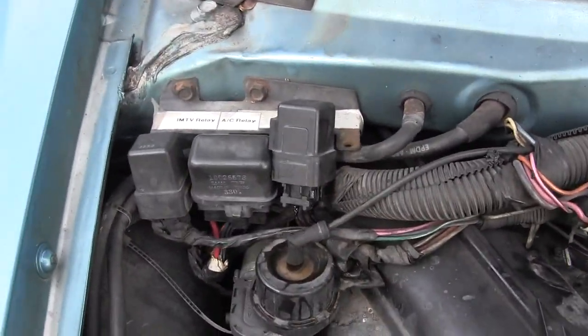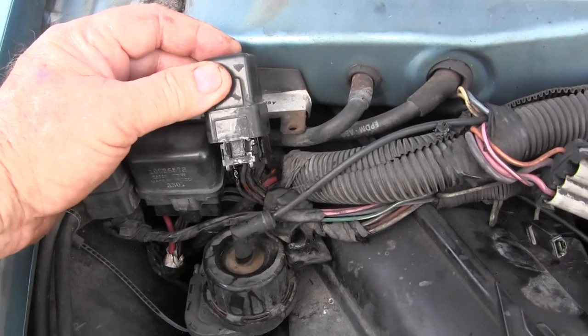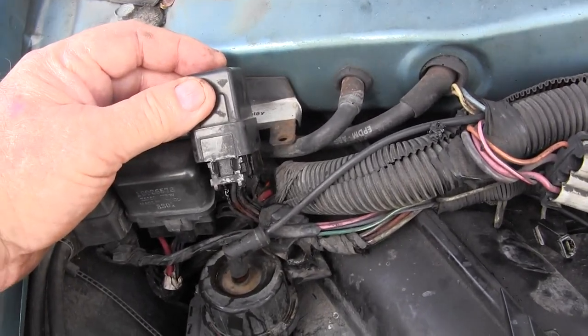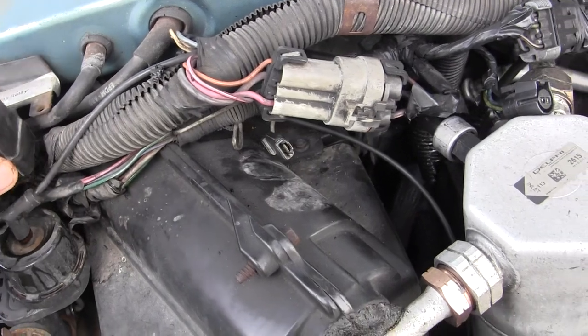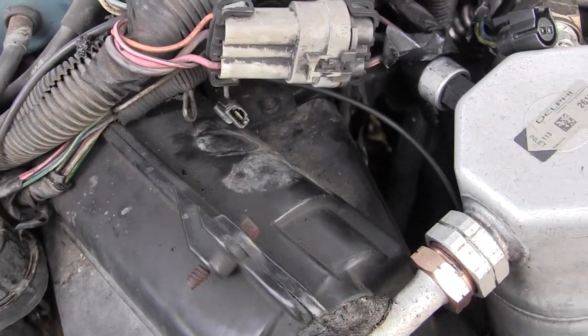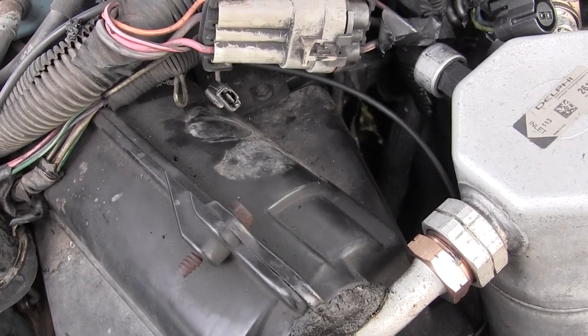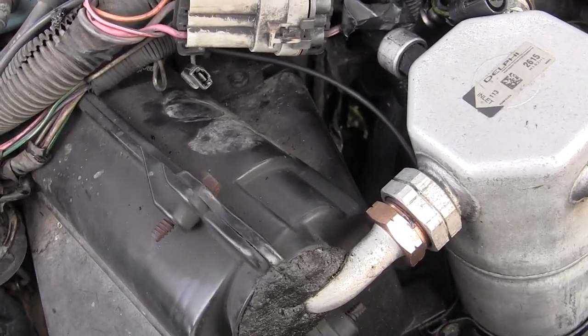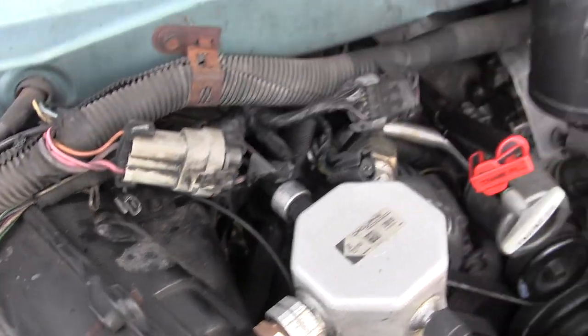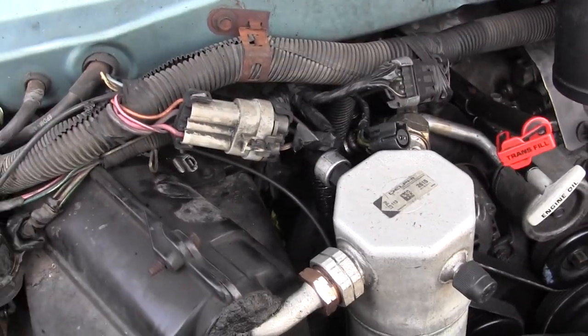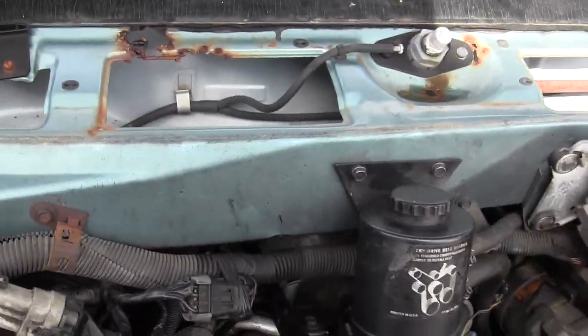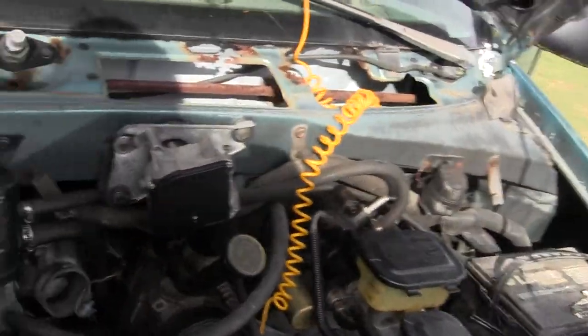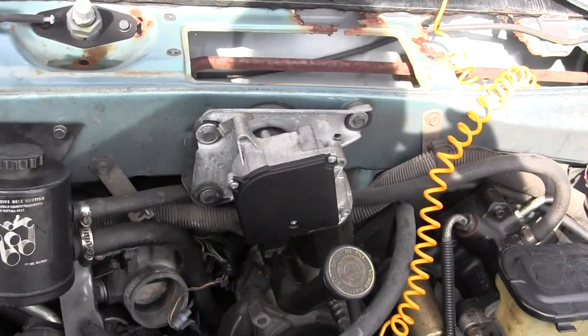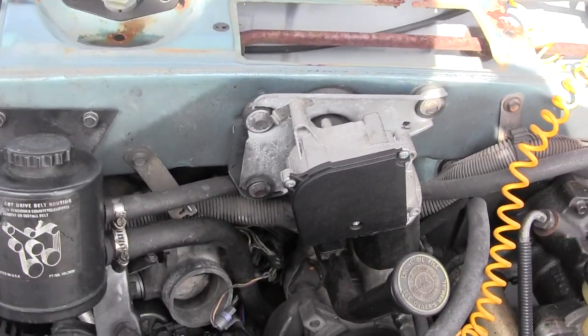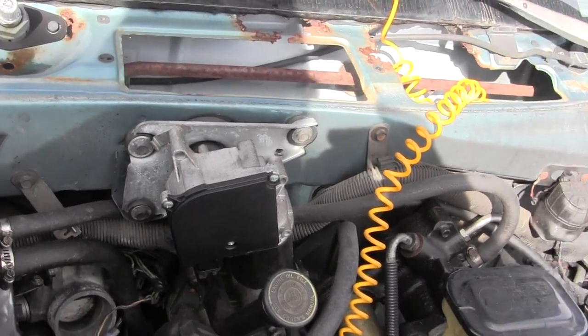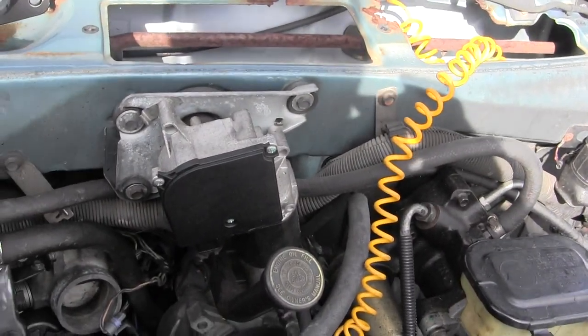But the thing I said wrong was you won't get any power on the load side of this relay unless you have oil pressure. I can simulate the correct oil pressure with a resistance of between 30 and 140 ohms for the reading on the gauge, but to make that relay work, it takes a ground. It has a tipping point where it gives you a ground if your oil pressure is enough, and I don't know the spec on it—I'd have to look it up.